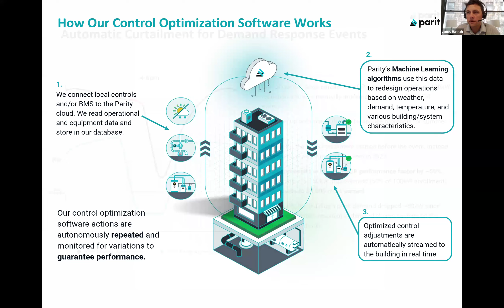As you get more in tune with what's going on in the building, you can typically push the savings to a higher level over time. This type of thing might yield somewhere between 5 and, on the high end, maybe 20% in savings, whereas deep retrofits can get you well over 40, 50 plus percent as you start doing bigger projects. So there's a number of different pathways you can take here.